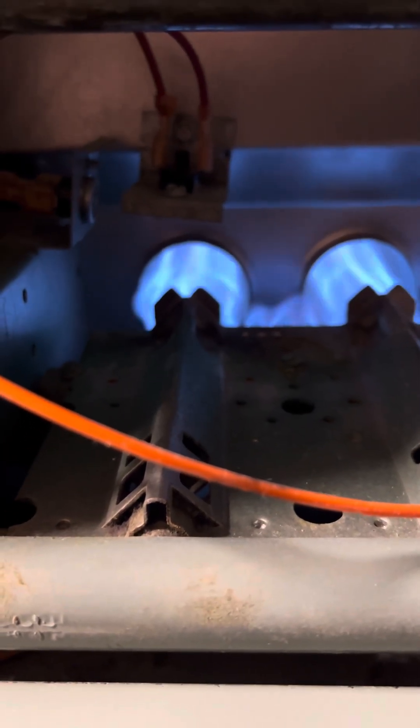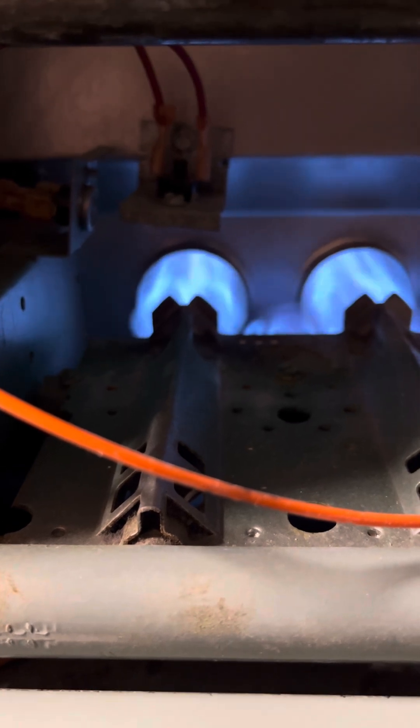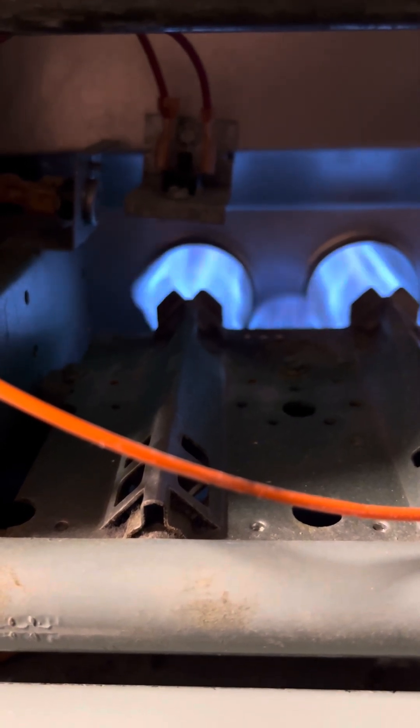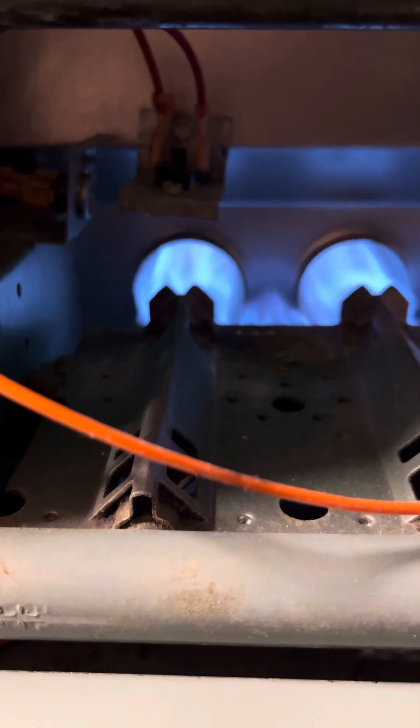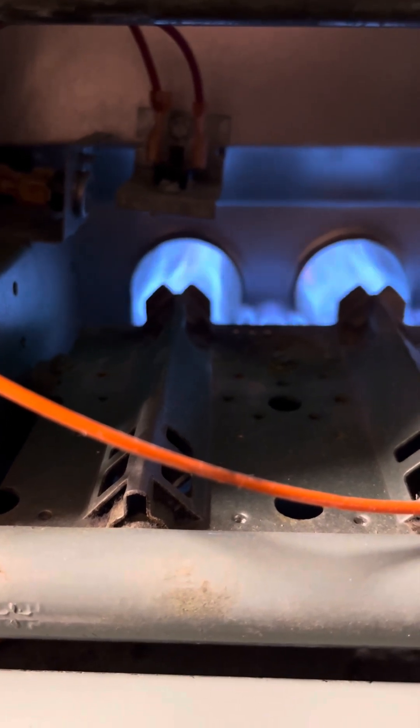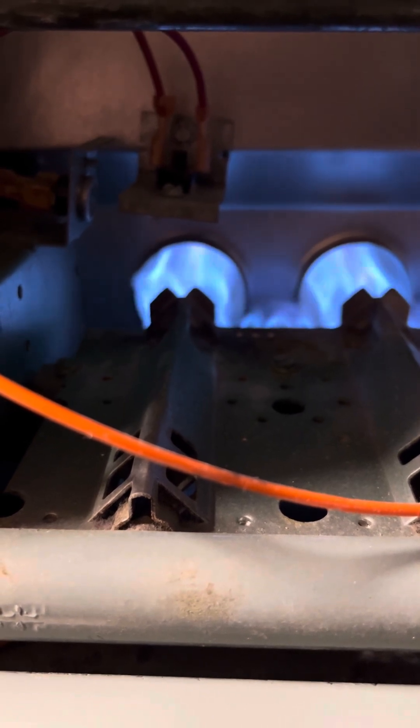I suspect that the initial problem the customer was having was that the system was overheating. They noticed that it would turn on and off a little bit more frequently. It would blow cold air sometimes. Probably run for 15 minutes, shut off, blow cold air for 5 minutes, run another 10 minutes, shut off, blow cold air for 5 minutes.